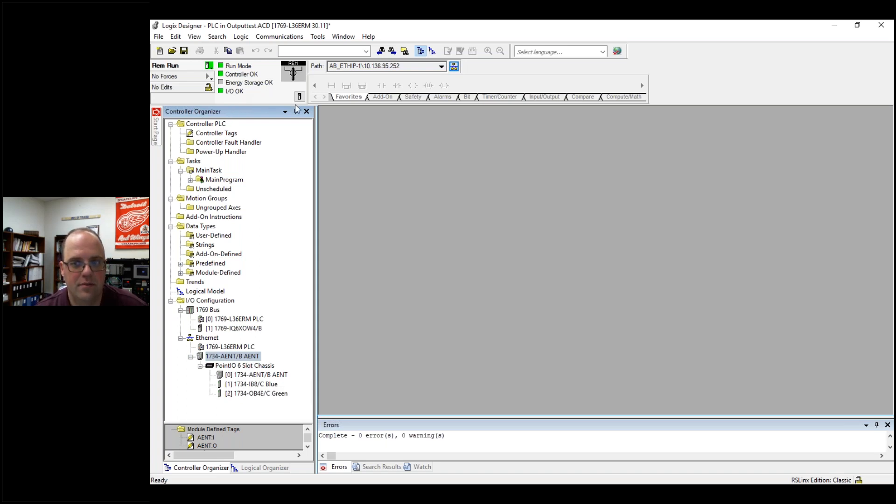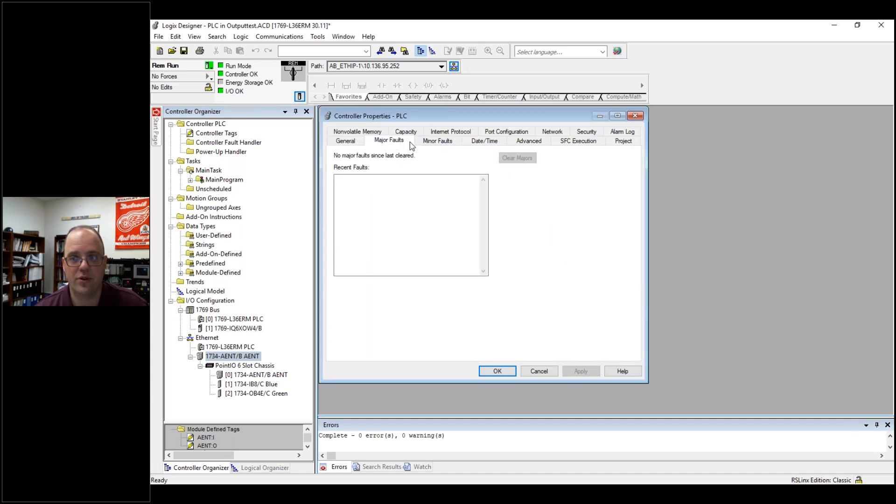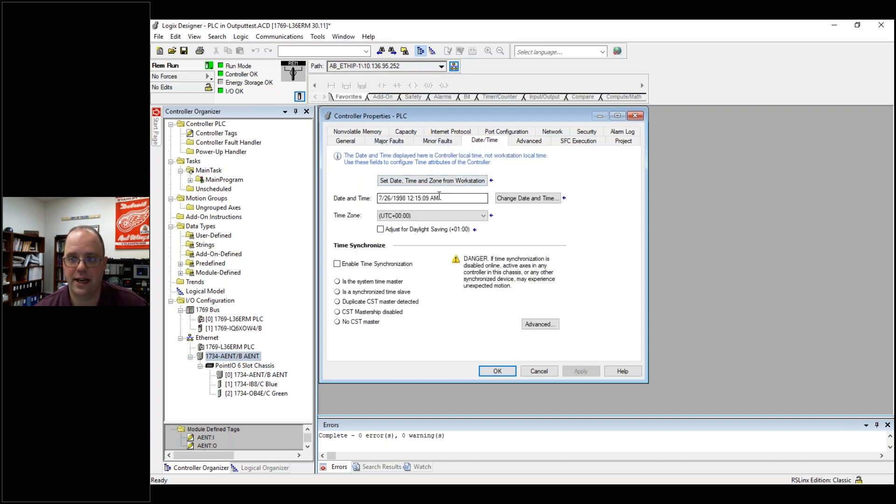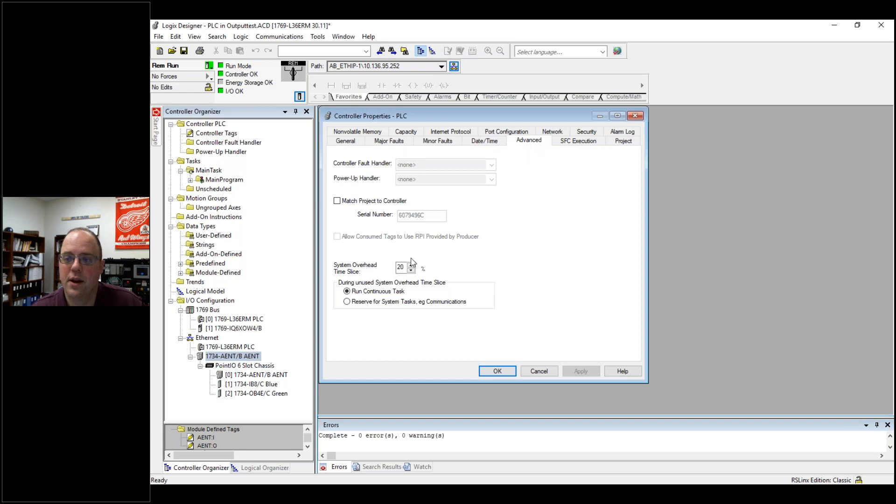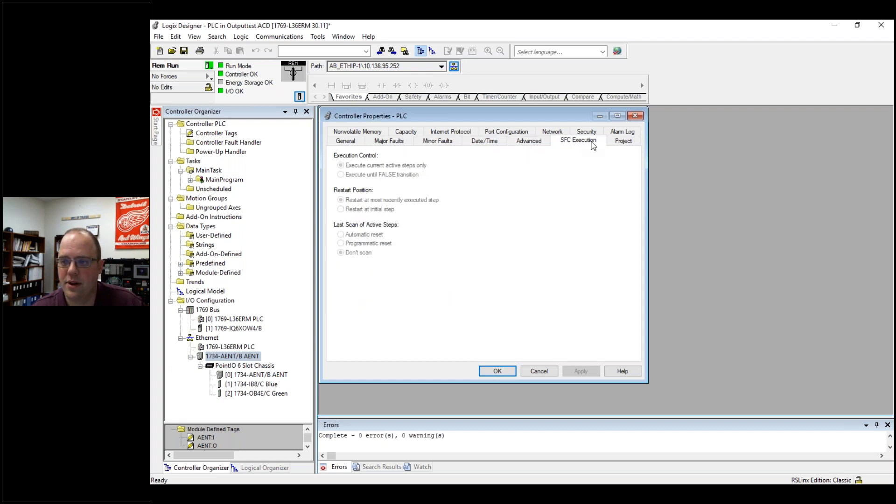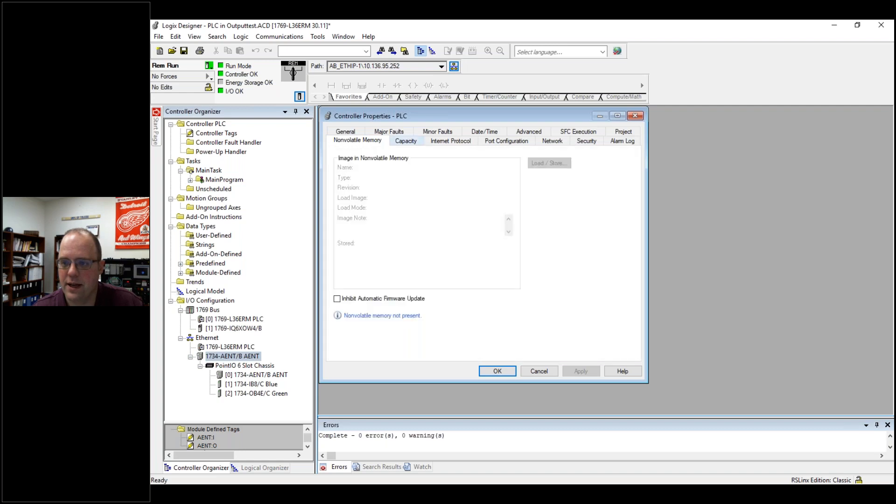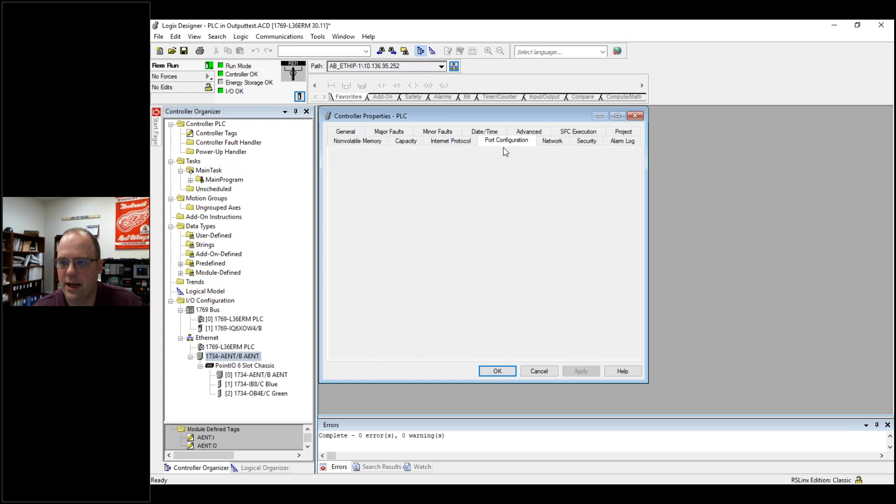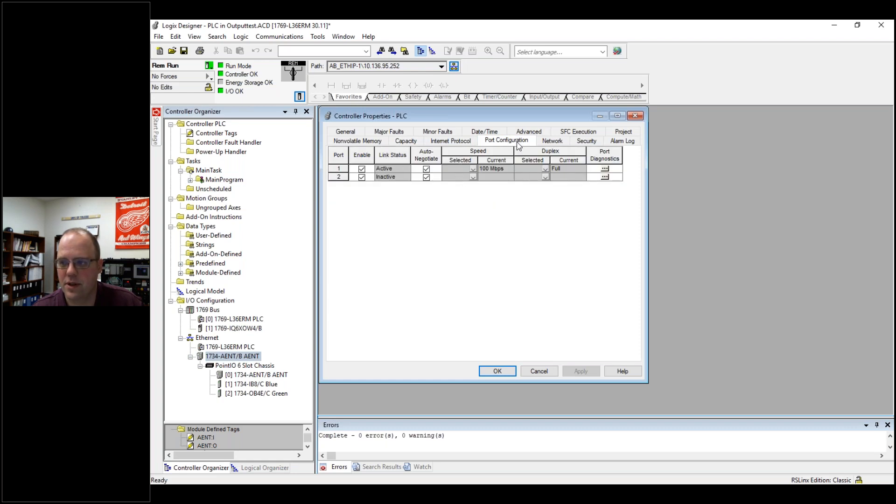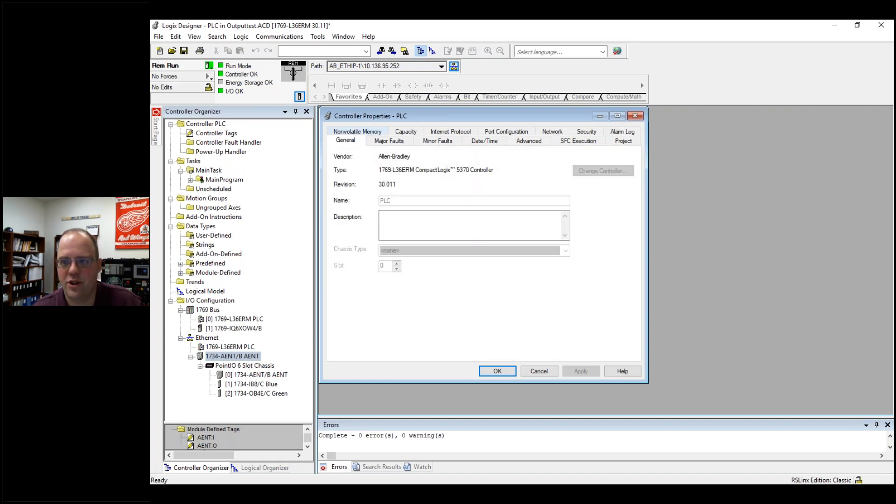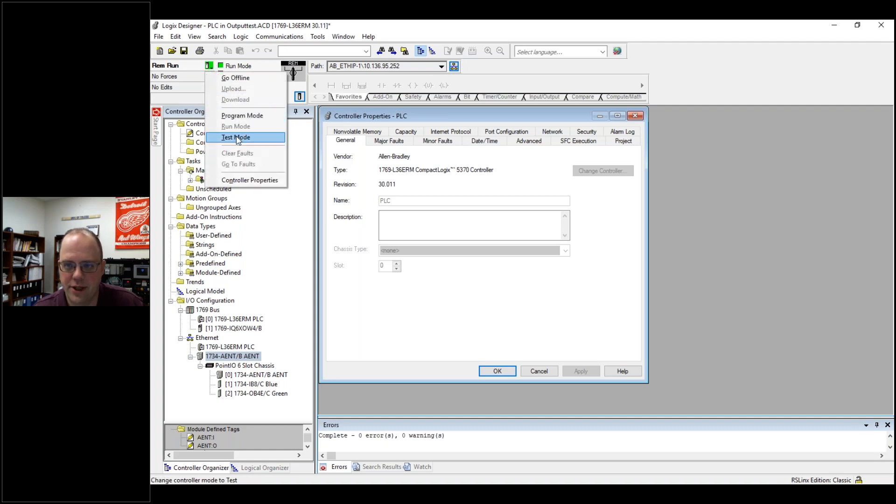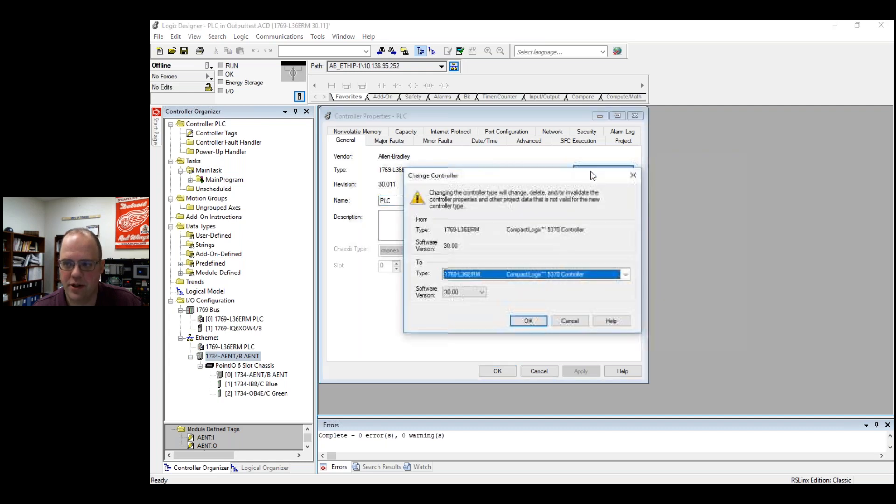Since I'm here, if I click on this little icon here, I can go dive deeper into my processor. I can see the revision, I can clear faults. So if you get a fault, you can go online, click here, and you can clear faults. You can change the date and time. Now look, is this the date and time? No. So I'll set that date and time from my workstation. Now it matches my workstation. I can even adjust for daylight savings time. Some of this stuff is extra. Here's the project name. I can see how much memory I'm using, what my capacity is, what my ports that I'm using are. I can look at my network and all the other fun stuff. But really I would go here to general and tweak things. Now in industry, if I wanted to change the revision type and do this to something else, I would click on change controller, and this is where I can change things, but keep the program the same.